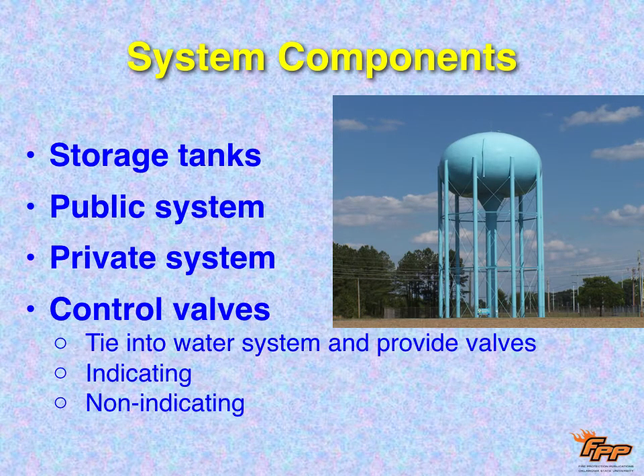Here's a typical picture from the Midwest. They put the water in storage tanks, elevated tanks like this, because they don't have the hills like we do. We're going to put our storage tanks on hills, and it's going to drain from there down into the streets, and then into the homes. Now, the fire protection system has to be separated from any fresh water, and we'll talk about that in a second. With the water supply throughout our communities, there's both public and private. Sometimes there's private systems, but government always has some kind of oversight over these. All the systems have to have control valves to be able to control the flow of water and to be able to shut it down if they have to work on something. And those valves are broken up into two kinds, indicating and non-indicating. I'll show you some examples in a couple of slides.